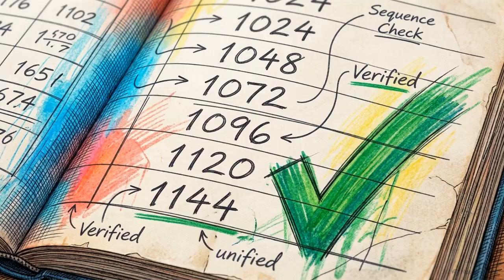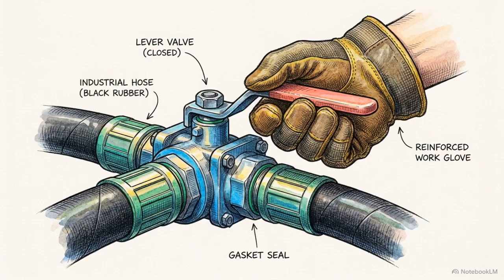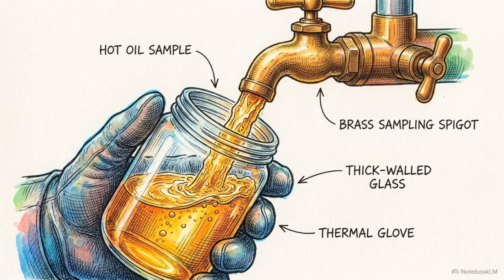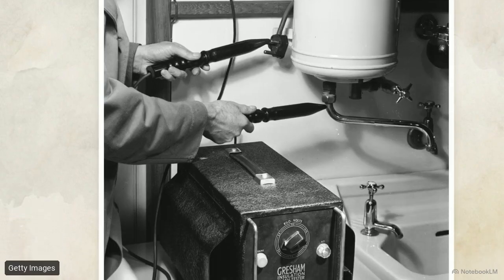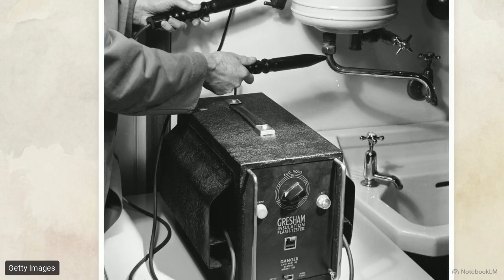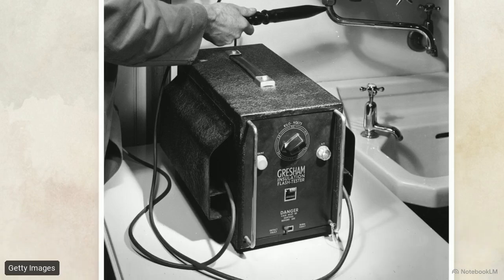Continue circulation until your logs show a rising IR tendency across 6 consecutive readings. If the filter plant loses power or trips, close the valves immediately to prevent an oil overflow. Once the IR readings stabilize, draw a hot oil sample to perform a breakdown voltage or BDV test. The hot oil sample must withstand at least 60 kilovolts RMS before breakdown occurs to meet the safety standard.